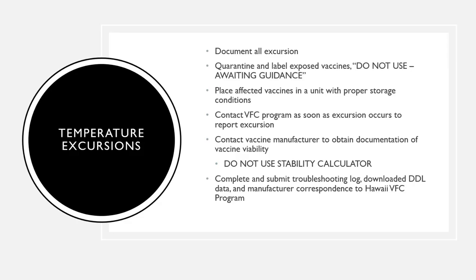So temperature excursions. Document all excursions. Quarantine and label any exposed vaccines do not use, awaiting guidance. And take those vaccines and place them in a unit with proper storage conditions. Let us know as soon as the excursion occurs and contact the vaccine manufacturer to obtain documentation of vaccine viability. Do not use the stability calculator that is found online because it doesn't take into account previous excursions that the vaccine may have been exposed to. Complete and submit the troubleshooting log, the downloaded DDL data, and manufacturer correspondence to the Hawaii VFC program at the email address hawaiivfc@doh.hawaii.gov.